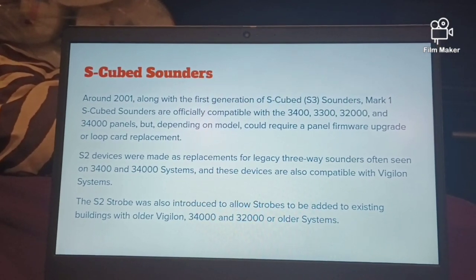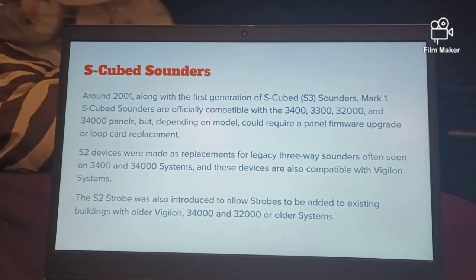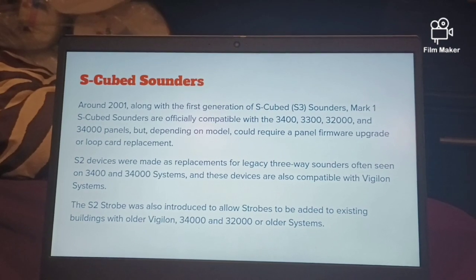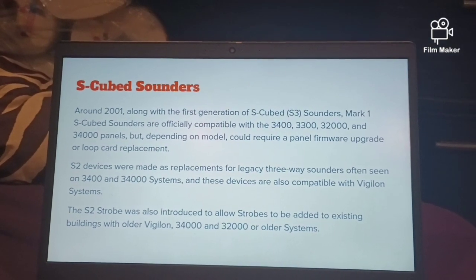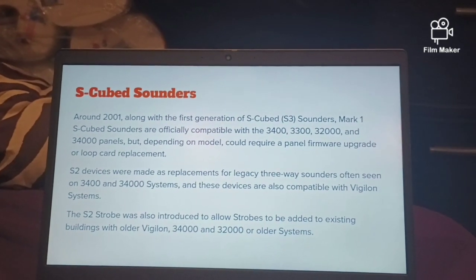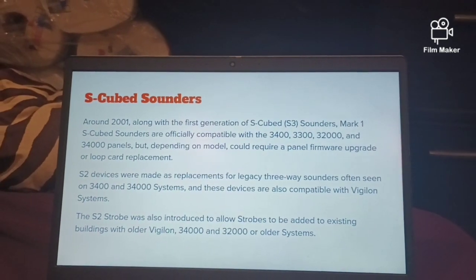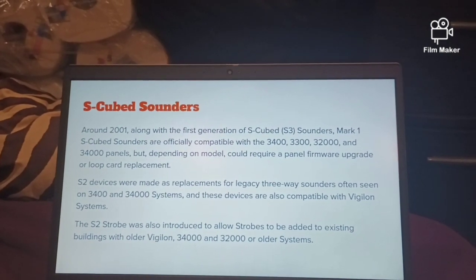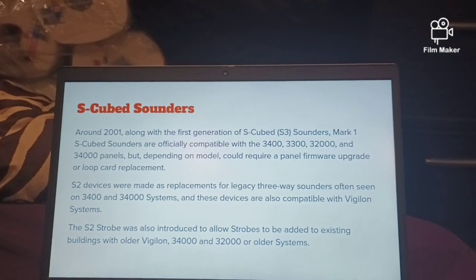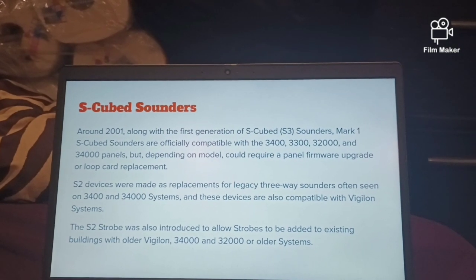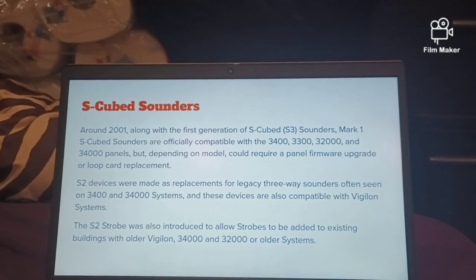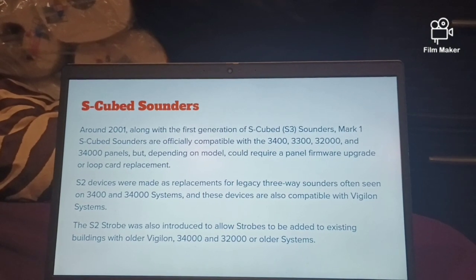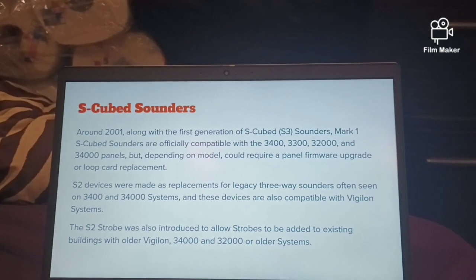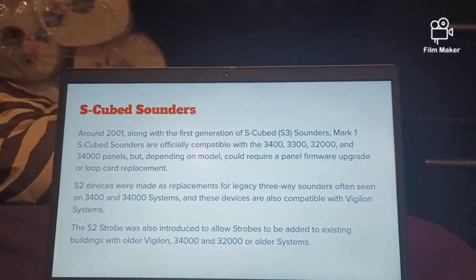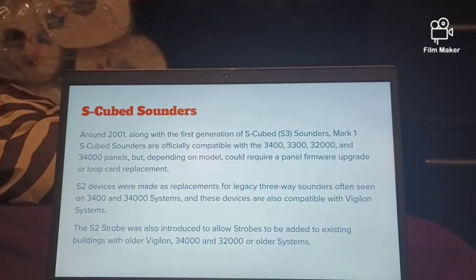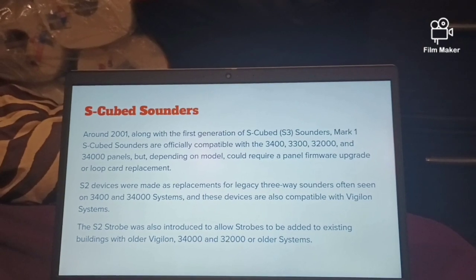S-Cubed sounders. Around 2001, along with the first generation of S-Cubed S3 sounders, Mark 1 S-Cubed sounders are officially compatible with the 3400, 3300, and 32,000 and 34,000 panels, but depending on model, could require a panel firmware upgrade or loop card replacement. S2 devices were made as replacements for legacy three-way sounders as often seen on 34,000 or 3400 and 34,000 systems, and these devices are also compatible with Vigilon systems.